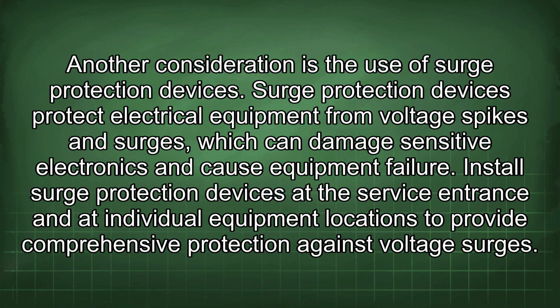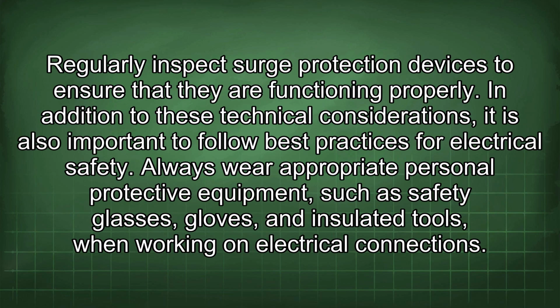Another consideration is the use of surge protection devices. Surge protection devices protect electrical equipment from voltage spikes and surges, which can damage sensitive electronics and cause equipment failure. Install surge protection devices at the service entrance and at individual equipment locations to provide comprehensive protection against voltage surges. Regularly inspect surge protection devices to ensure that they are functioning properly.